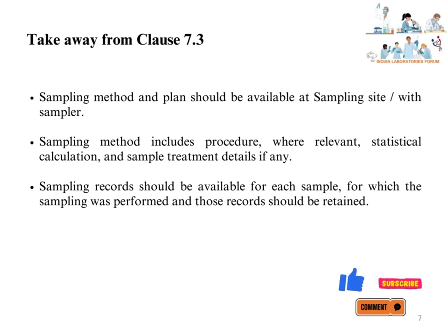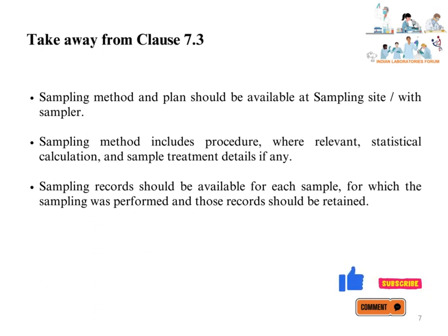Takeaway from Clause 7.3: The laboratory should have a sampling method and plan, and those should be available at the sampling site with the sampler. The sampling method includes procedures for sampling and, where relevant, statistical calculations for arriving at the number of samples to collect, and details of sample treatment if any. The sampling record should be available for each sample for which sampling was performed, retained as per requirements, with details essential for sampling, testing, and reporting of results.